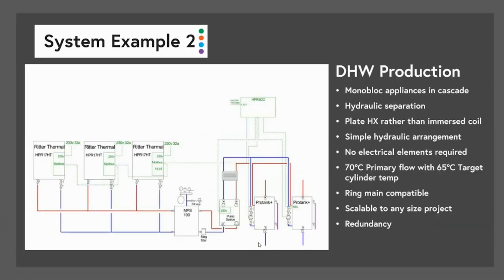So this is another example of multiple heat pumps, but this time the hot water production only. So that's another thing that R290 is very good at. Hot water produced and stored in the tanks at above 60 degrees, so 65 degrees. Here we can set up a 70-degree primary flow temperature into them and recover these tanks really, really quickly through a heat exchanger. Here's the pump station here.